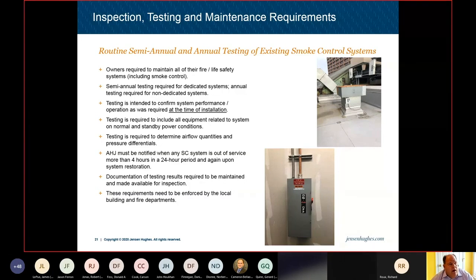The other piece of why semi-annual testing is required is, as you all know, there's requirements for testing of all fire and life safety systems, but unfortunately, by far, the smoke control systems for those existing systems are the most neglected and the least likely to have regular inspections, testing, and maintenance done on them. So there is a reason why some of the codes also not only enforce that, but the codes did adopt a weekly self-test requirement for new smoke control systems because of the lack of maintenance and inspection and testing that happens on smoke control.